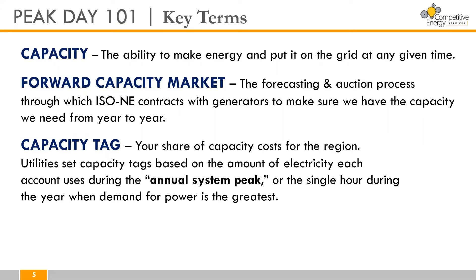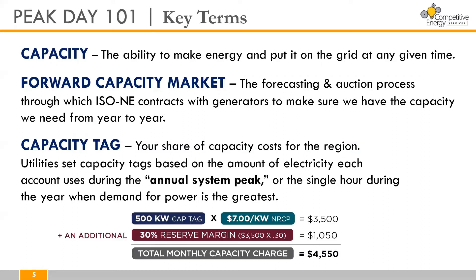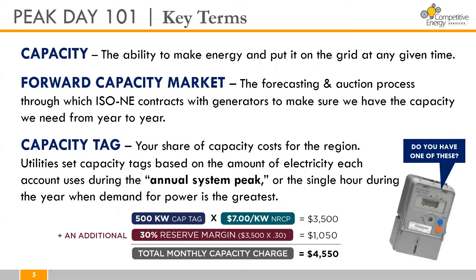So how are these capacity charges determined? In short, the answer is your capacity tag. Capacity tags are assigned based on the amount of electricity each account uses during the annual system peak — the single hour during the year when demand for power is at its greatest. There is a calculation to determine the impact of your capacity tag on your costs, but we won't be getting into the weeds on the numbers today. It's also important to mention that not everyone can control the price they pay for capacity — only accounts with interval meters, otherwise known as telemeters, can control their capacity tag.